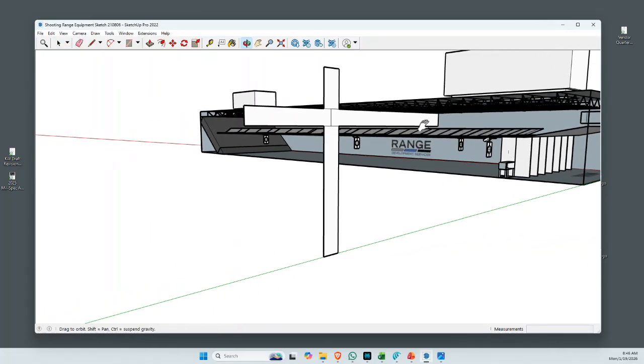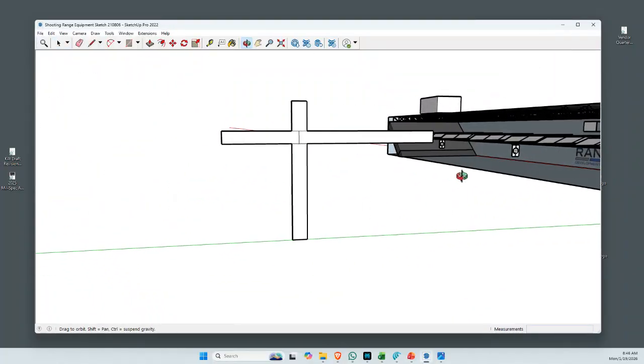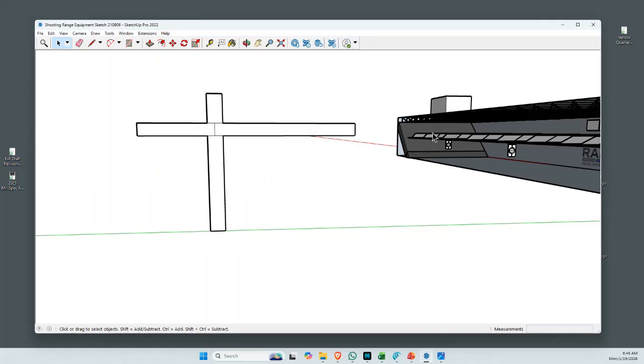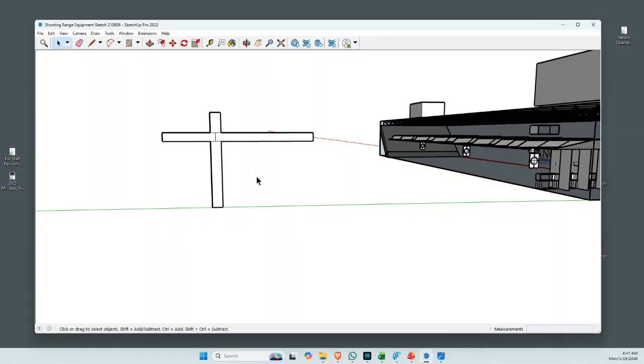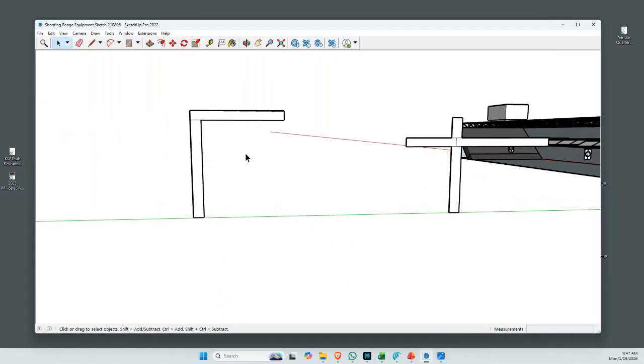So the other element I'll mention here is just this little quick drawing that I put together. This is a profile of these walls. And what we want to do, particularly with a hollow core concrete plank, is avoid this situation, because sound will jump over that wall, even if it's sealed up and so forth. It's just a joint connection that lets too much sound, in our experience, into the other non-range portions of the facility, and can disrupt normal conversations. Secondarily, if this is an exterior wall, we want to minimize the amount of sound that is emitted from the building.